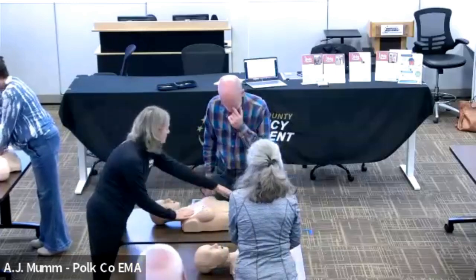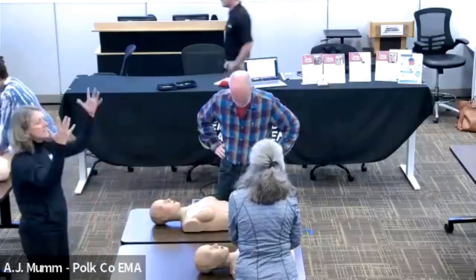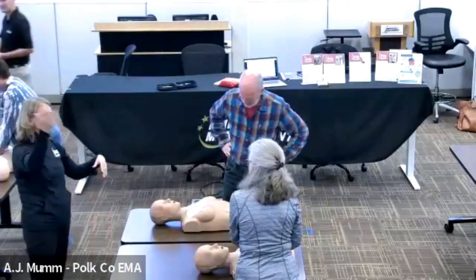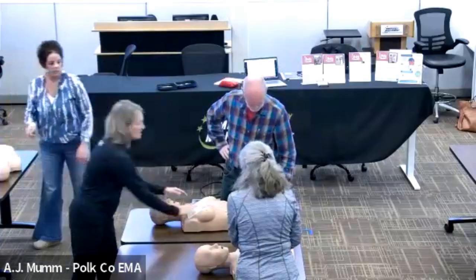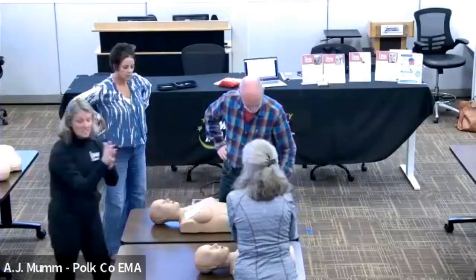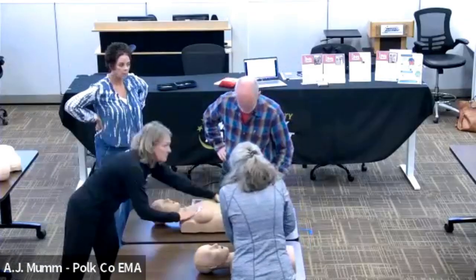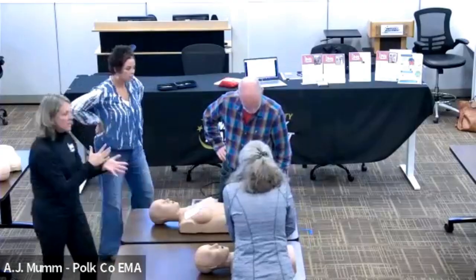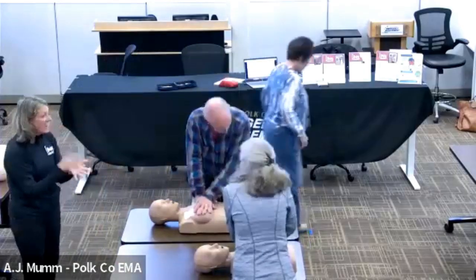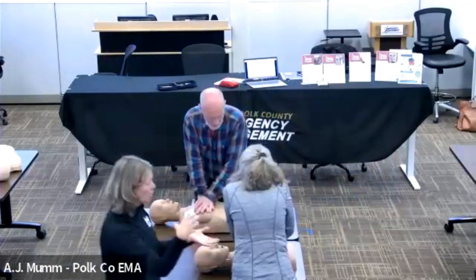It's telling you to put the pads on because they weren't all the way pushed down. We had an instance here where it kept saying over and over again, put the pads on the patient. It's because the pads weren't quite as sticky, since we've been using them a lot today, and it wasn't stuck on there. So if it keeps telling you to put the pads on and they're still on there, just make sure you push them really good so that it can sense it. It's telling you that it can't sense that the pad is on there.